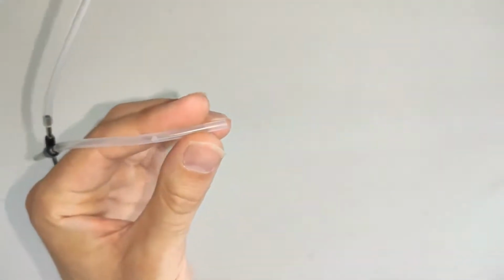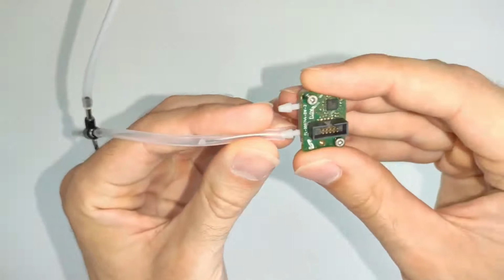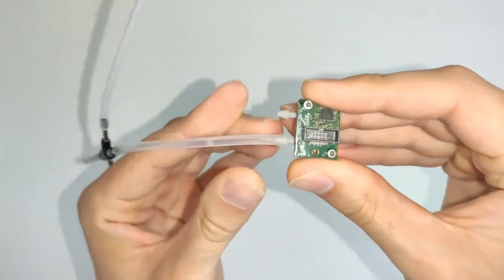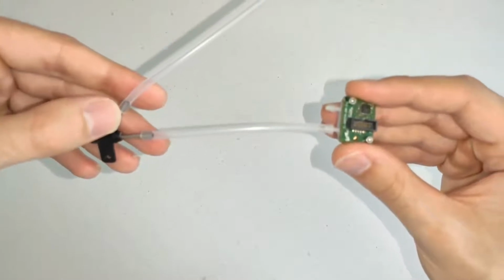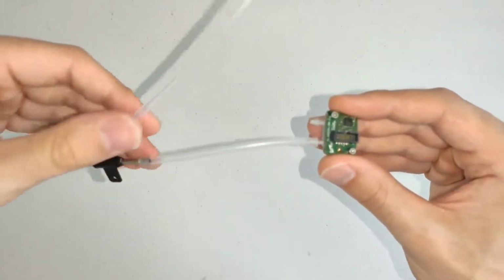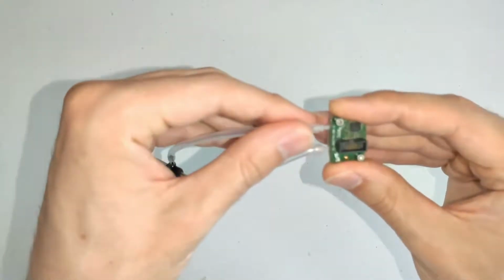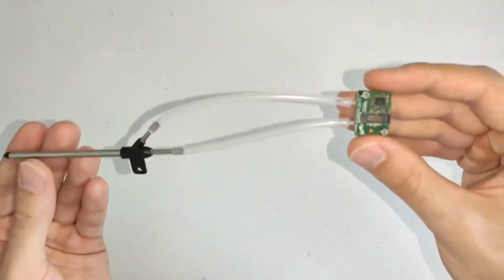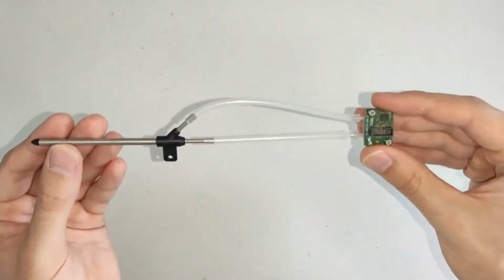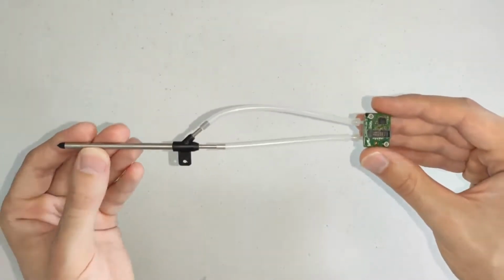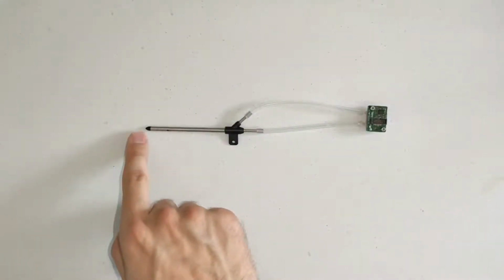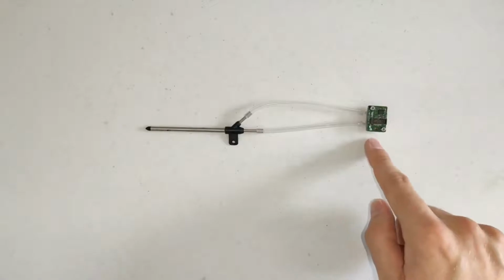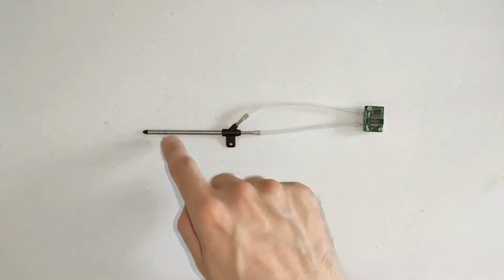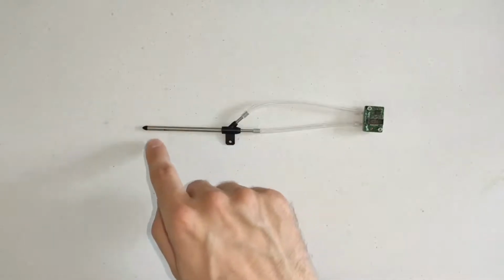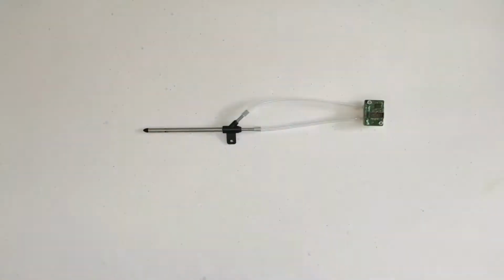You're going to want to connect the tapping that goes to the tip of the pitot tube to the upstream port of the FLS110, and connect the pressure tapping that goes to the circumference to the downstream port of the FLS110. Hopefully you can see I've connected it that way. The flow in the system will go from the tip of the pitot tube down to the FLS110, then back to the pitot tube and out the pressure tappings on the circumference - that's the direction of flow.